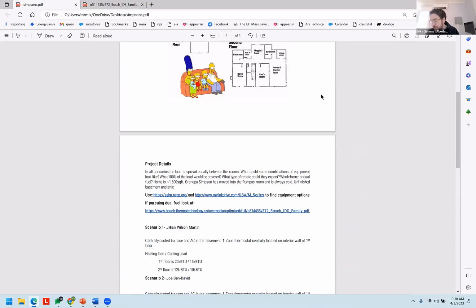Yes, that is a reality, but there's a question about the return. If you're putting in a central heat pump down in the basement for the first floor and also for the second floor, there's a big question of where the return is going to be located. You wouldn't want zone 1 to be the first floor and zone 2 the second floor, but have a central return on the first floor. So typically, if you're putting in a second air handling unit, I'd recommend putting it up in the attic and having a central return on the same floor as the supplies.